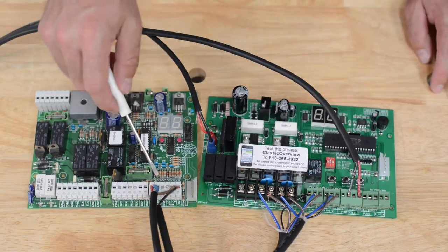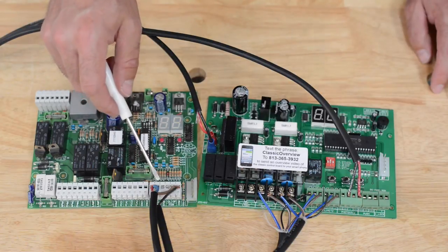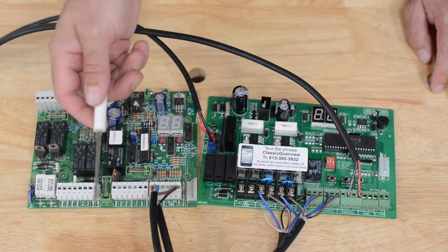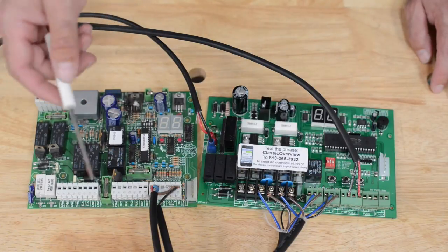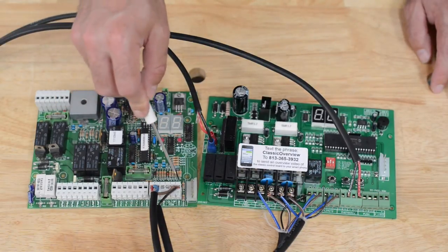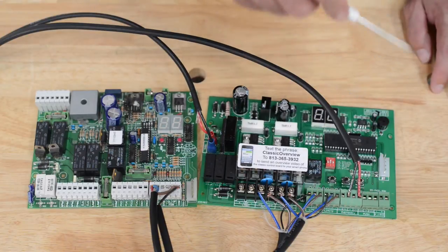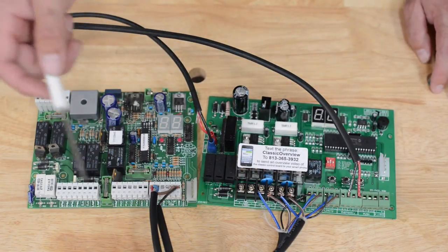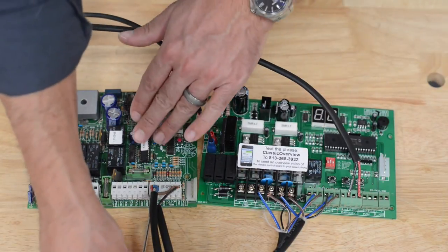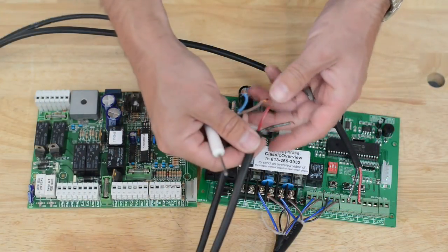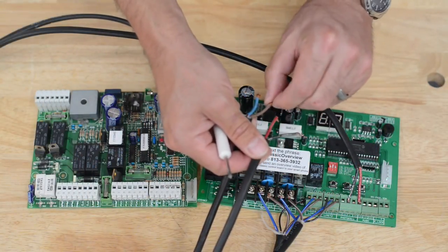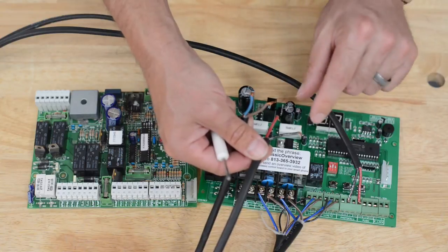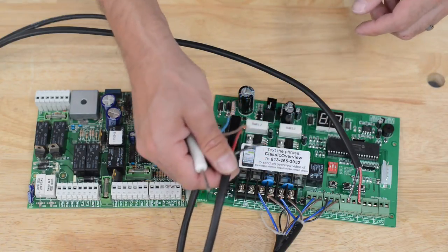On the old board, any opening device, be it an exit sensor, which is an automatic device, or a standard device like a keypad or push button, always went to open A and common. On this board, it's going to be slightly different. So I'm going to take the two wire sets out. Now we separate them out. Again, my blue and my brown are my two leads for my exit sensor. My red and my black are my two leads for my push button.